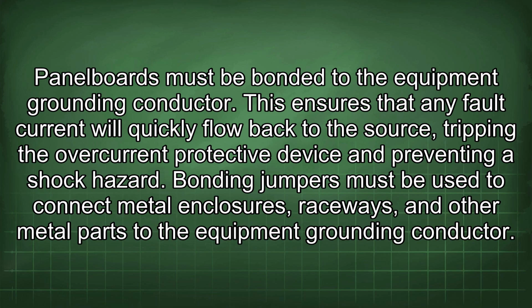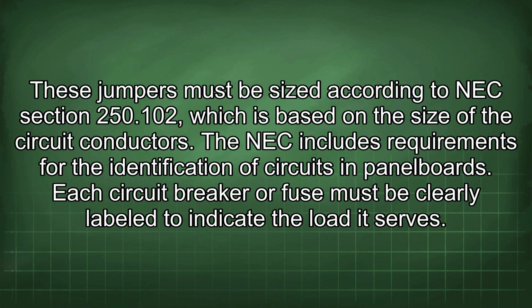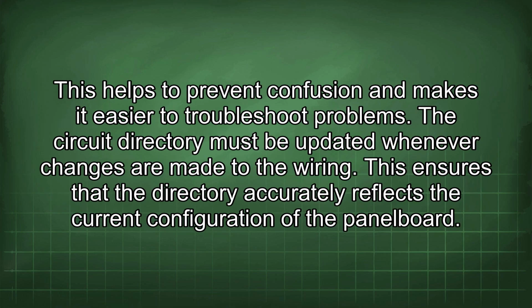a shock hazard. Bonding jumpers must be used to connect metal enclosures, raceways, and other metal parts to the equipment grounding conductor. These jumpers must be sized according to NEC section 250.102, which is based on the size of the circuit conductors. The NEC includes requirements for the identification of circuits in panel boards. Each circuit breaker or fuse must be clearly labeled to indicate the load it serves. This helps to prevent confusion and makes it easier to troubleshoot problems. The circuit directory must be updated whenever changes are made to the wiring. This ensures that the directory accurately reflects the current configuration of the panel board.